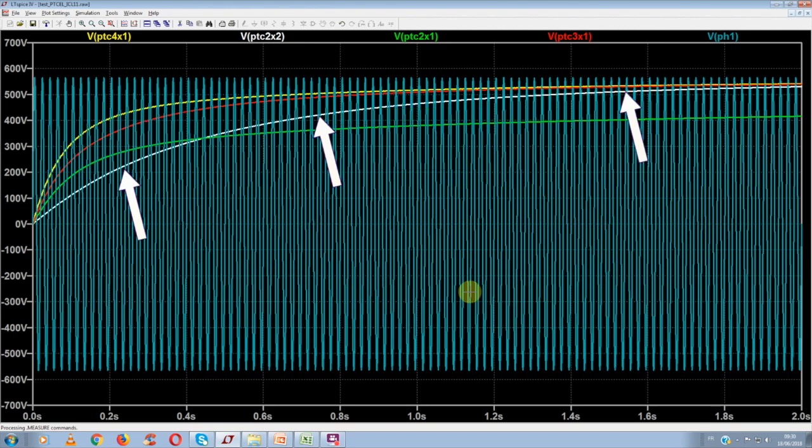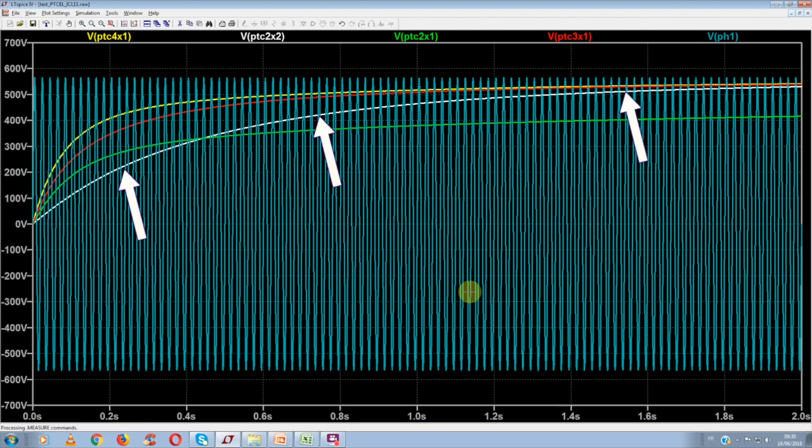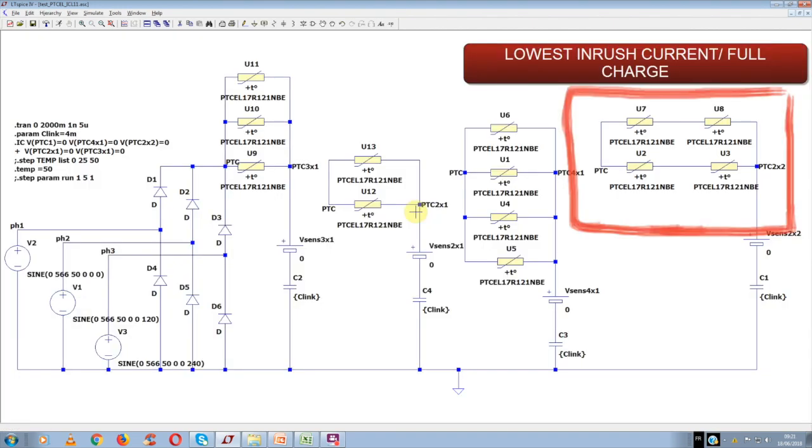And the white curve, which simulates the configuration of the two parallel branches of two PTCs in series, shows also a full charging of the capacitor. And as this last case also gives the lowest surge current, this combination is obviously the best solution.